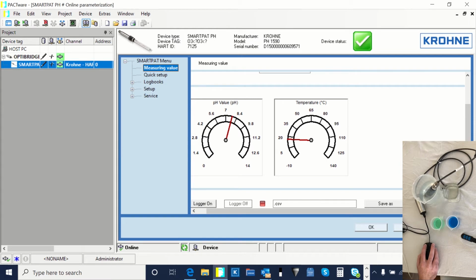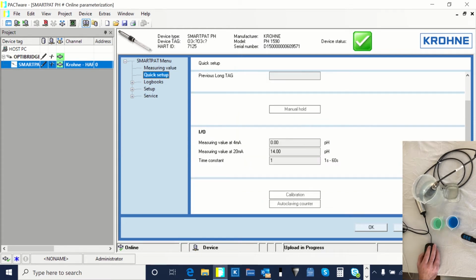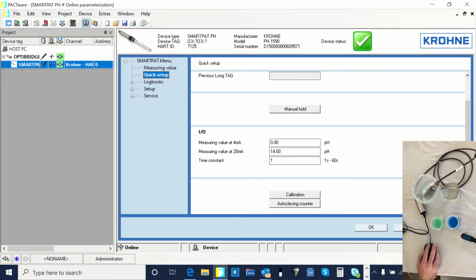Okay, so what we're going to do is come here to quick setup and have a look here, and you can see it takes a little while to click in. We can see what our pH probe is set to, which is the 4 to 20 milliamps set to 0 to 14 pH. If we want to do a manual hold, for this situation where we're doing a bench top calibration, we don't need to hold the last value.